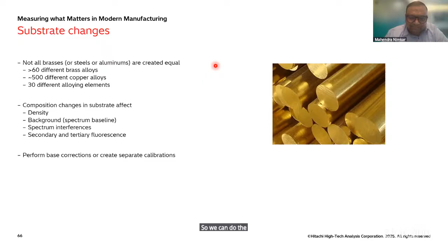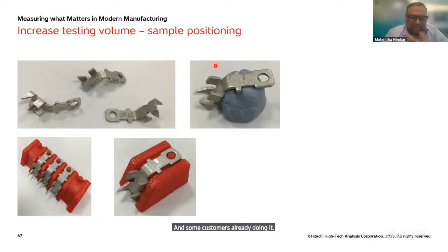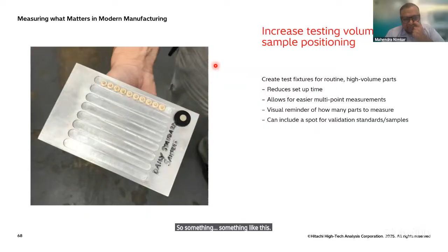Sample positioning makes a lot of difference. If your sample position is not correct, there is always variation in the result. Some customers we always recommend to make jigs, or some kind of fixture, so you can keep the sample in the same position all the time. If you're working three shifts, all your people will keep the sample in a similar position, so there won't be any variation. We recommend this kind of trick to some customers, and some customers are already doing it. They sometimes even teach us. They make fixtures.